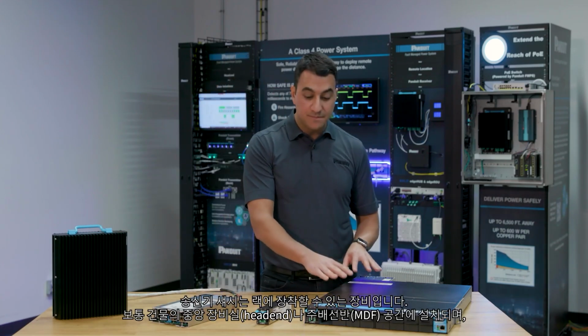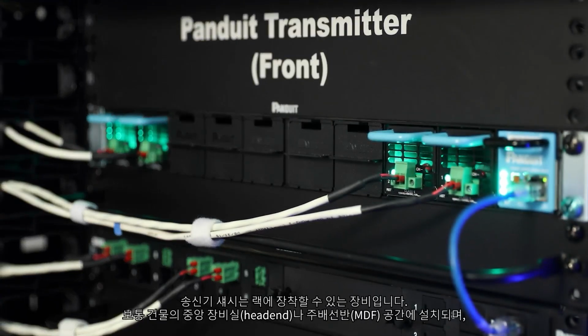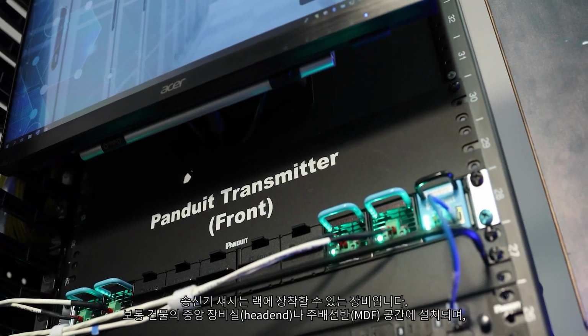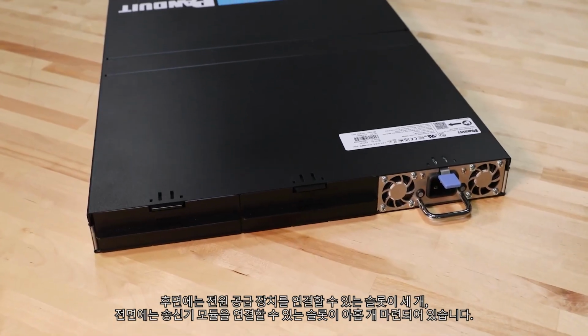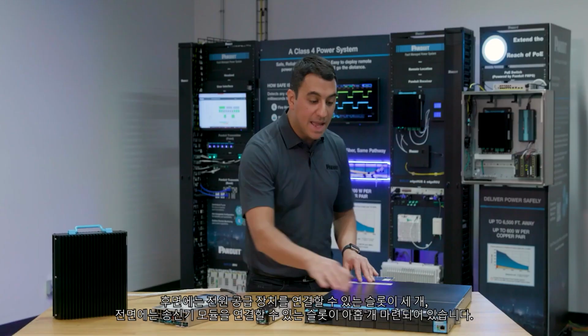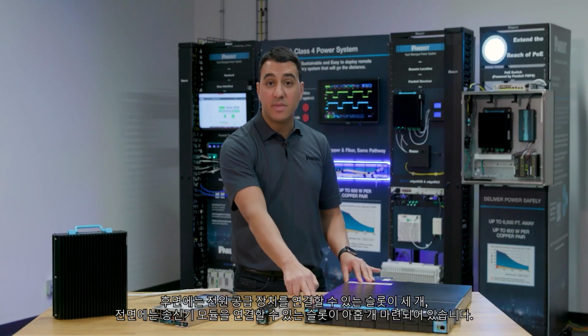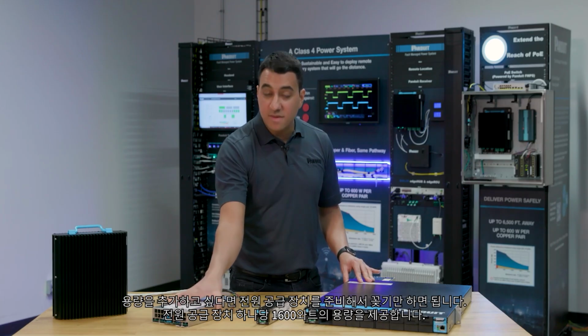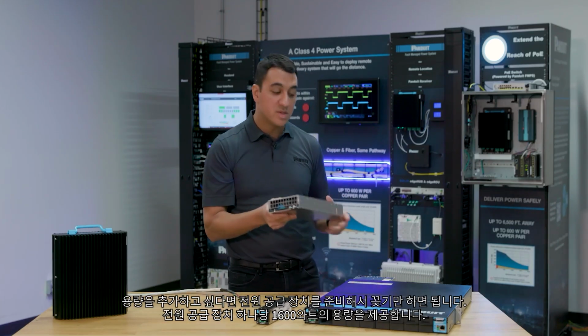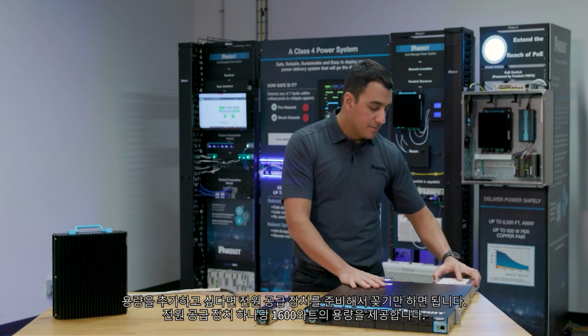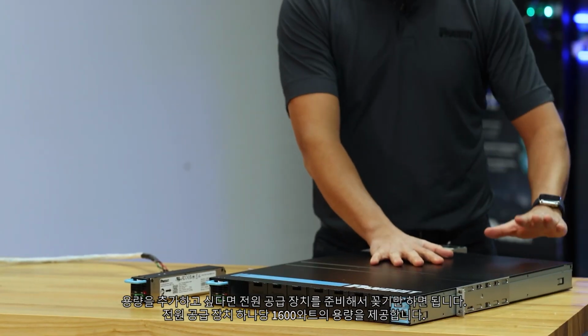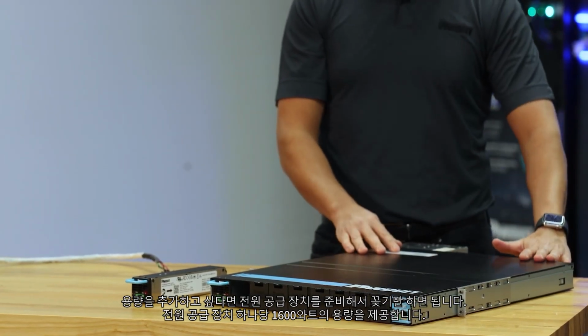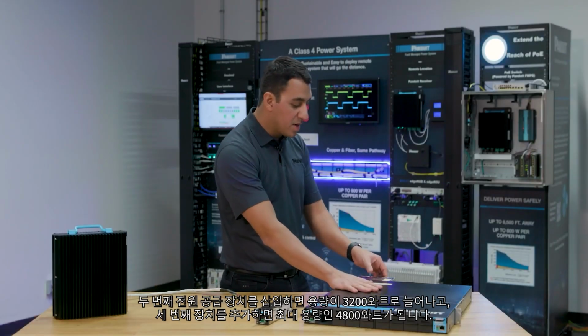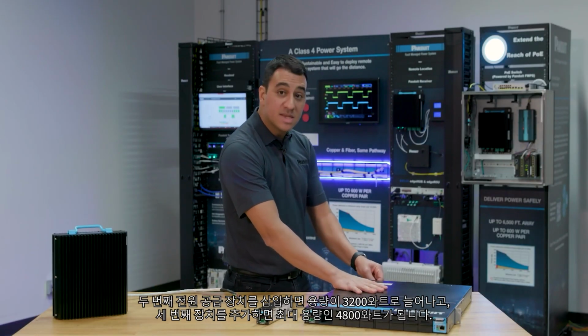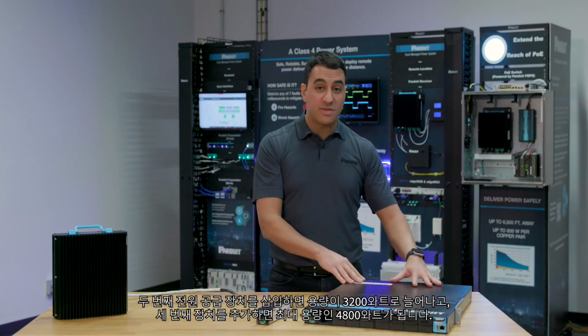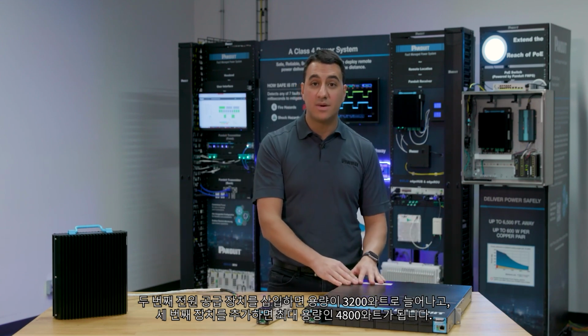The transmitter chassis is a rack-mountable unit, typically going to be sitting somewhere in the head end or MDF of your building. It has 3 slots in the back for power supply units to plug in, and it has 9 slots in the front for transmitter modules to plug in. So if you wanted to add capacity to this unit, you simply take a power supply unit and you plug it in. Each one gives you a capacity of 1600 watts. You slide a second power supply unit in. That gives you a capacity of 3200 watts. If you add the third, now you get the full capacity, which is 4800 watts.